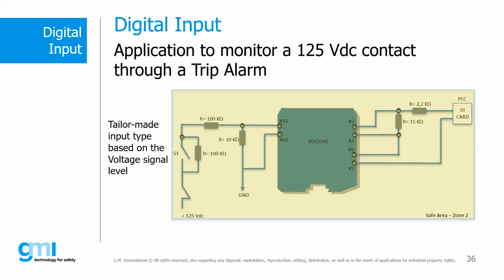In fact, using a trip amplifier and connecting it with a network of resistors to the contact in the field, we can obtain voltage levels at the input of the device that allow us to discriminate one state from another. Furthermore, by programming our trip amplifier with intervention thresholds, we can provide the PLC with a different state for each condition of the input contact, being able to distinguish the normal operating state of the contact from a fault state.